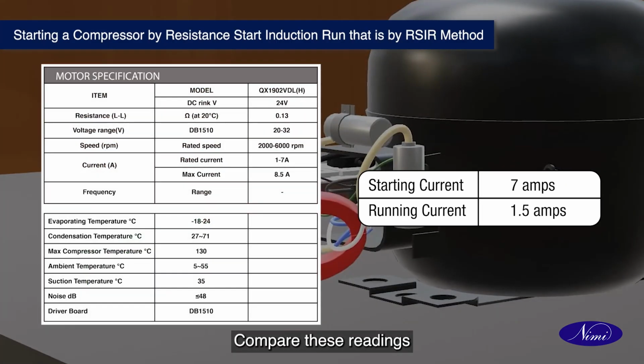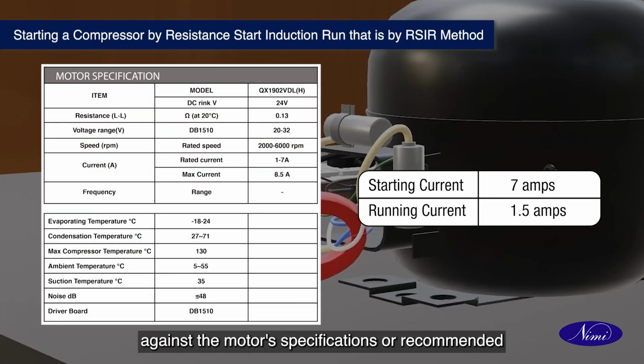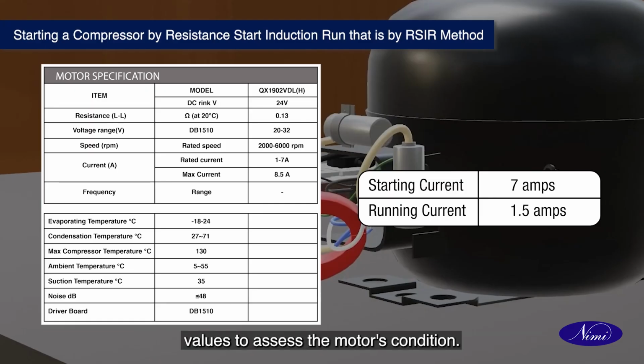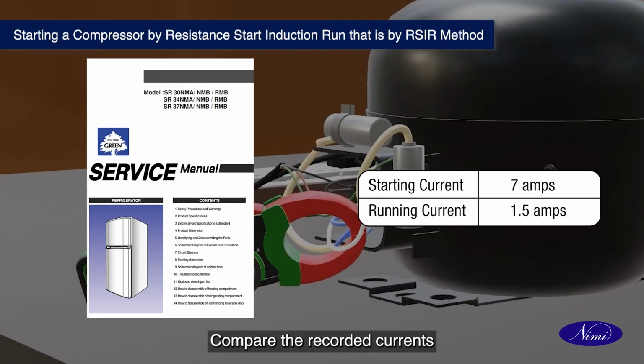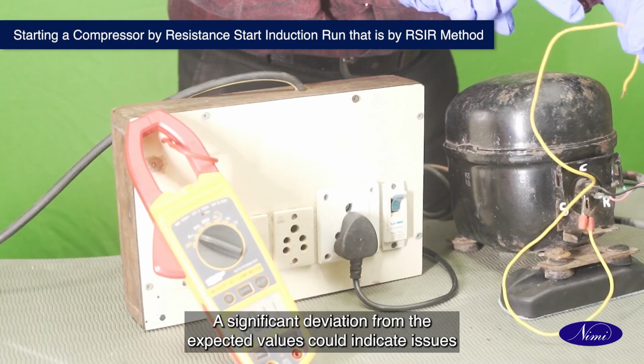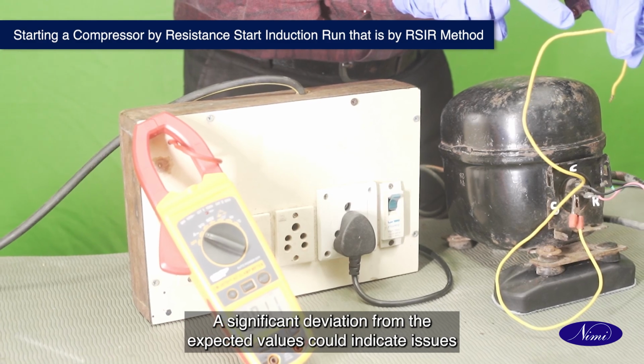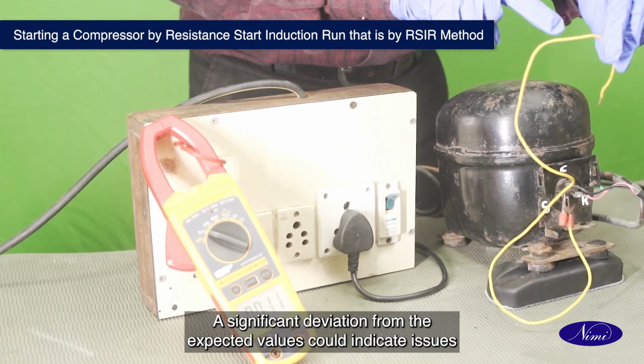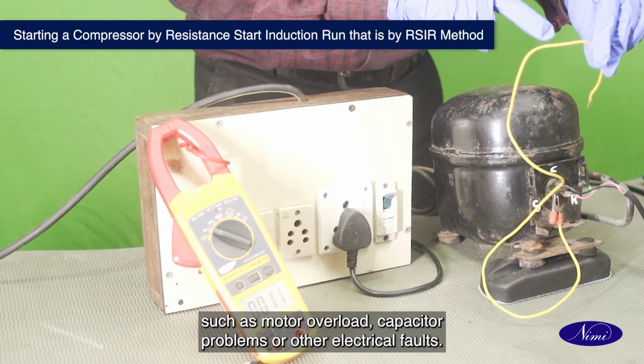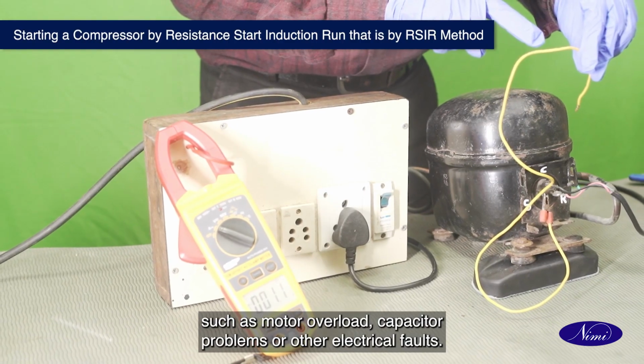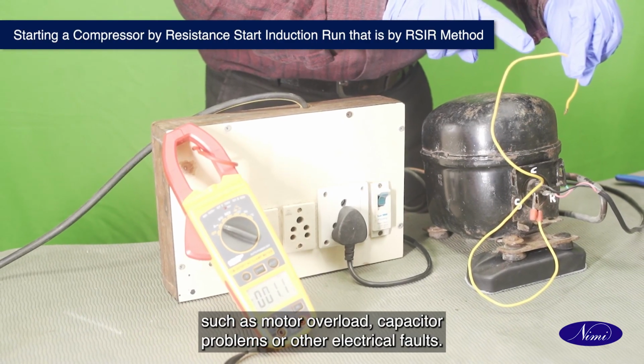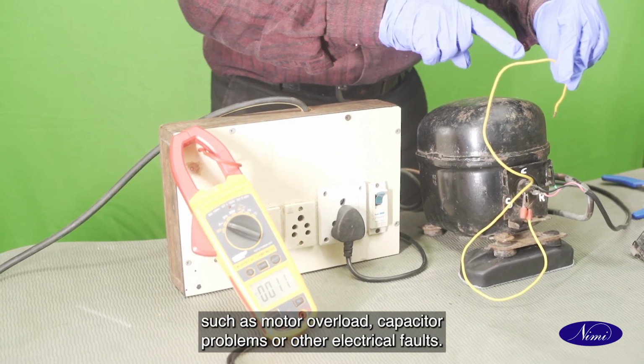Compare these readings against the motor's specifications or recommended values to assess the motor's condition. Compare the recorded currents with the manufacturer's specification. A significant deviation from the expected values could indicate issues such as motor overload, capacitor problems, or other electrical faults.